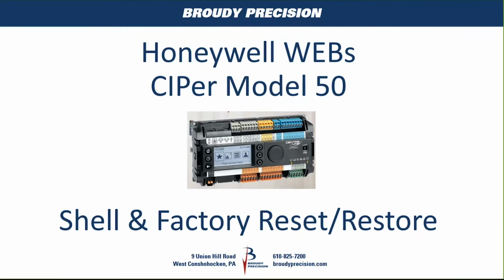I'm not going to go through all of the ins and outs of the controller. When we go through this video, if there are questions at the end, that's fine, we can do that. But really where I wanted to go with this was to make everybody aware when they're working with a CIPer Model 50, it runs Niagara. It's like a Jace. You hear people say it's the same as a Jace with I/O on board. One of the areas where it's very different is how shell mode is used and what you can do from there. I just wanted to point those features out now rather than later when I'm getting a support call when somebody's having issues, which is the reason for me making this video, because of a couple recent support calls.